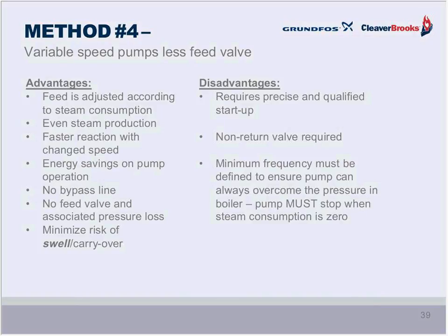Like anything else, there are advantages and disadvantages. The feed is adjusted according to steam. That's good. Even steam production. Faster reaction time with changes in speed. That's good. There will definitely be energy savings on pump operation, and we'll demonstrate that to you in our exercise. You get rid of the bypass line and the feed valve, and of course, the swell and carryover risk is minimized. But some disadvantages. This is a more sophisticated control, and it does require some very qualified startup.